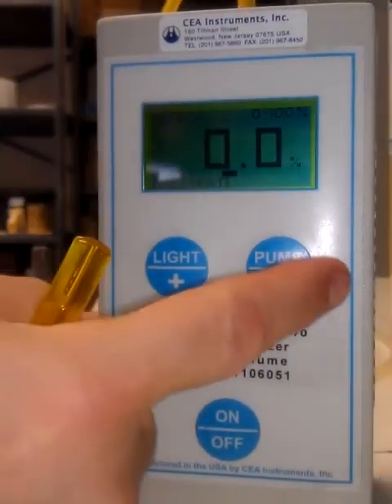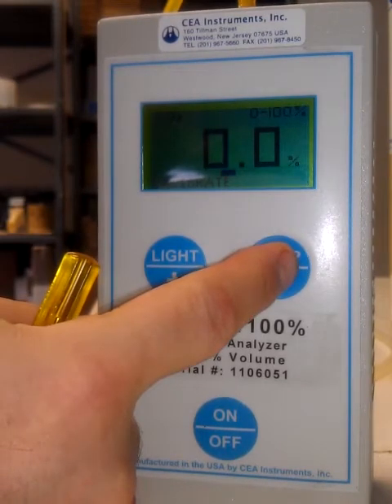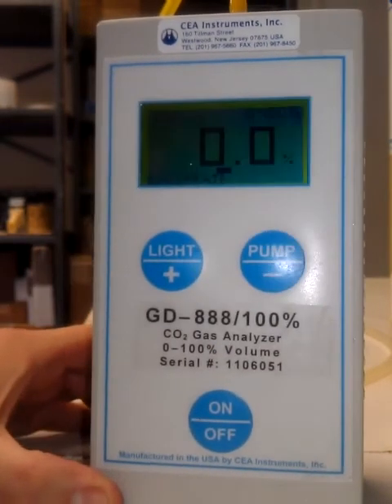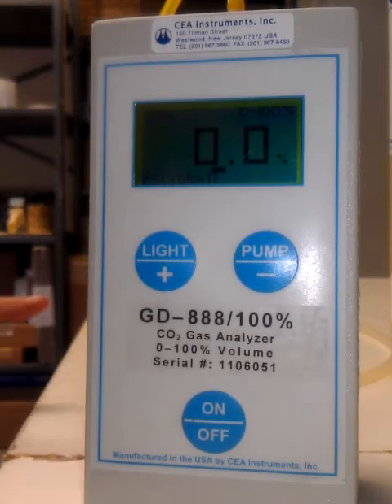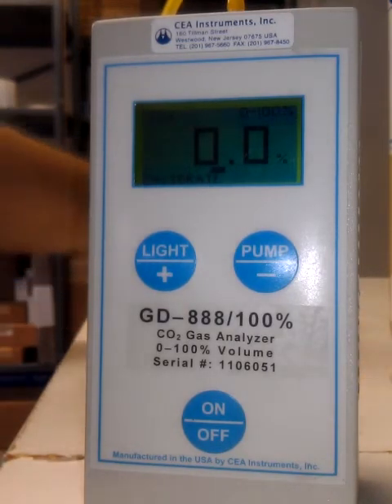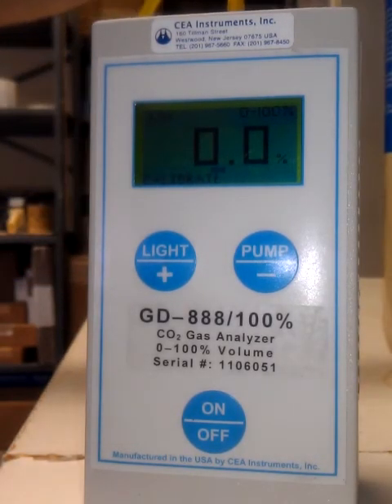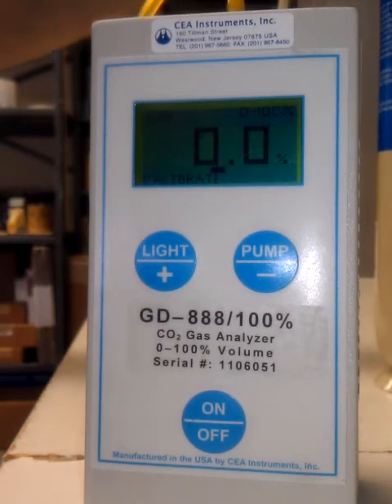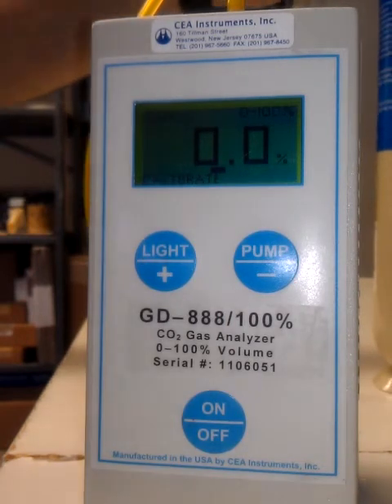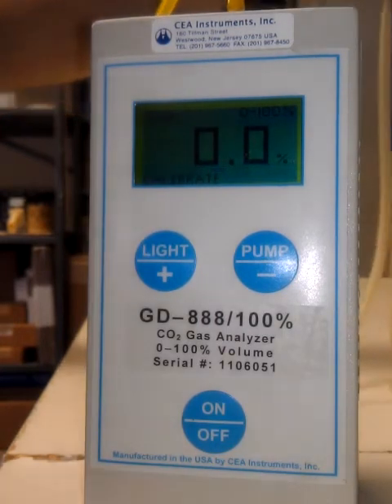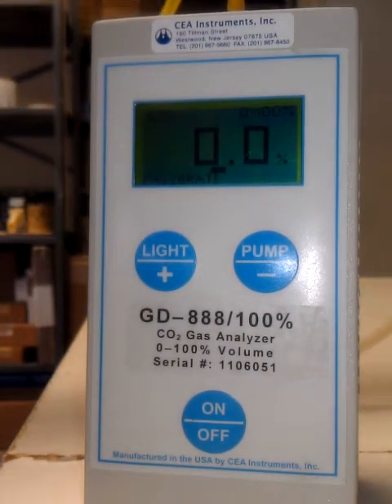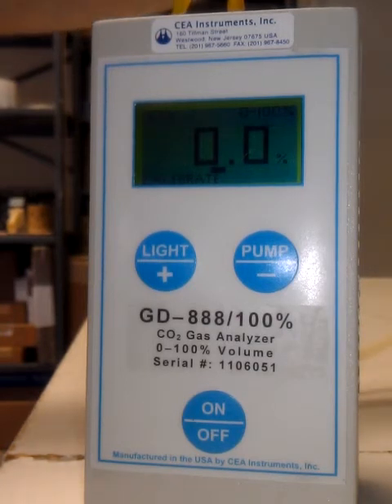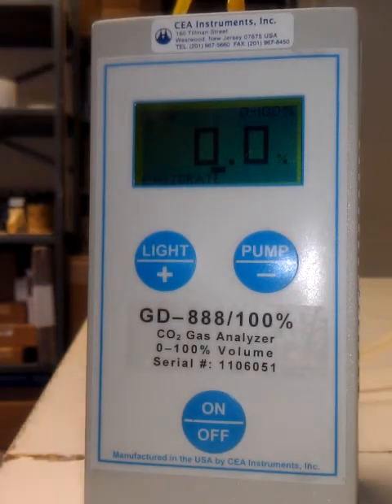Now you once hit the pump key to turn it off, and the pump will not turn on until you get out of cal mode. You introduce with about half a liter a minute. You can go 0.2 liters a minute, but try to stick at the most half a liter a minute of 99.9% cal gas. It must be 99.9 or 99.99, and it must be carbon dioxide for the 100% version. Turn on the gas, and the display will go up.